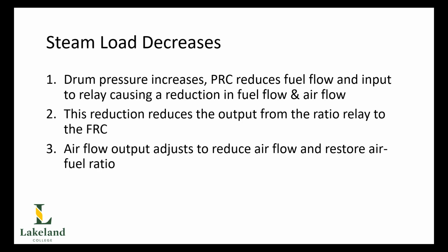So now that output going from our master pressure controller to our fuel control valve and across to our air damper drive via the modulating relay will reduce the firing rate. Now, our gas flow and airflow transmitters are going to see a reduction in airflow and gas flow. So the fuel to air ratio relay is going to compare those values to see if we're at the right ratio for the new firing rate, which of course we won't be because we're in the process of adjusting.